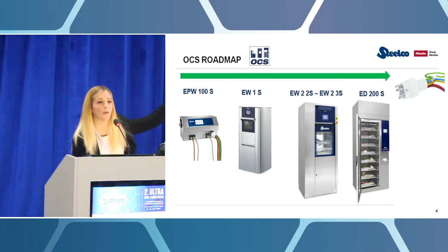You have to connect all the channels of the endoscope to correctly reprocess them. In the past, you needed to do this every time you moved from one stage to the next. Now, with the OCS system — which we also call the octopus because of the shape of the connector — you do that once, at the very beginning of the process.